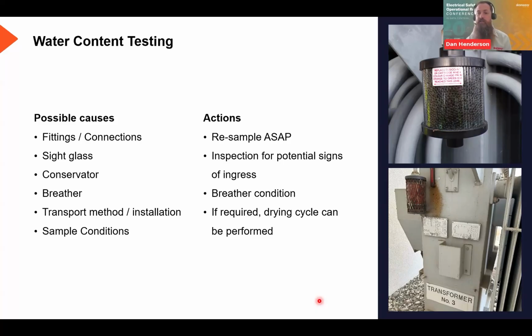As that saturates, as you can see in that picture there, that was originally orange, and when it's absolutely saturated, there's nothing that can get in or out. So that moisture can get absorbed then into the oil. So it's such a common thing, which costs pounds or dollars to fix, or in reality could end up costing you either business downtime or tens of thousands of dollars if you've got to replace the asset. So it's such an easy thing. Another thing that I've experienced is the transport method. So where I've had on first oil sample test of a new transformer, water content, and you can go back to the factory filling.